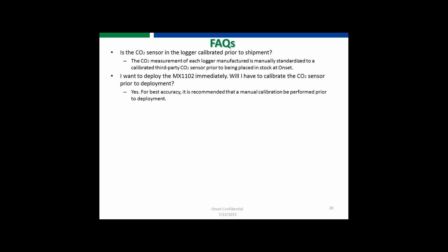So drift is affected by atmospheric conditions. We don't know what kind of conditions they might have been exposed to during shipment or how long they've been sitting on the shelf. So it probably makes sense when you get the device, take it outside, run a manual calibration, which is highlighted in that quick start guide, and then you'd be up and running. It'll only take you about 5 minutes or so.